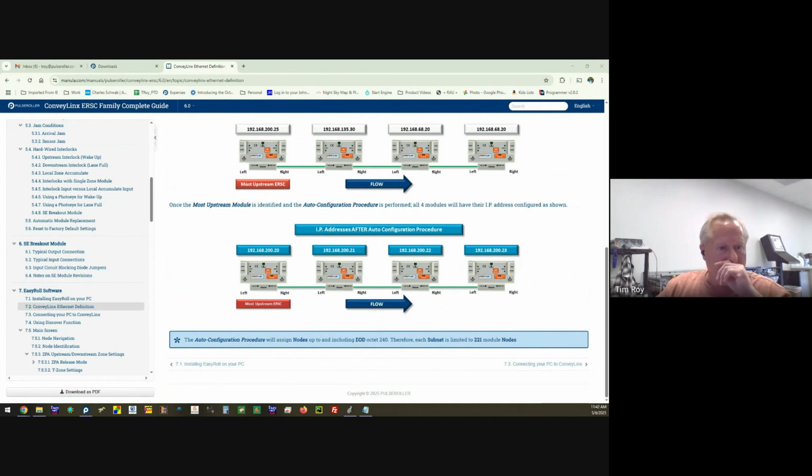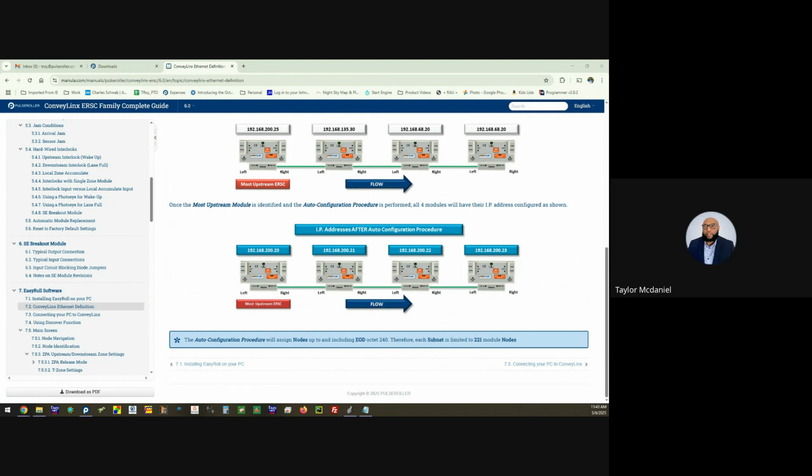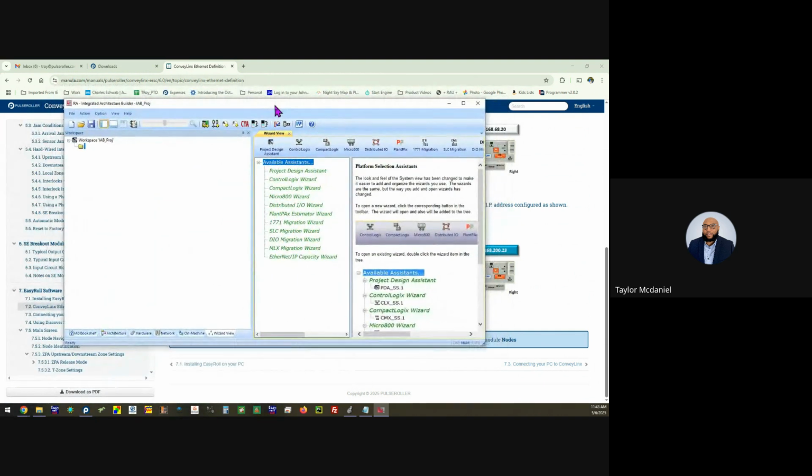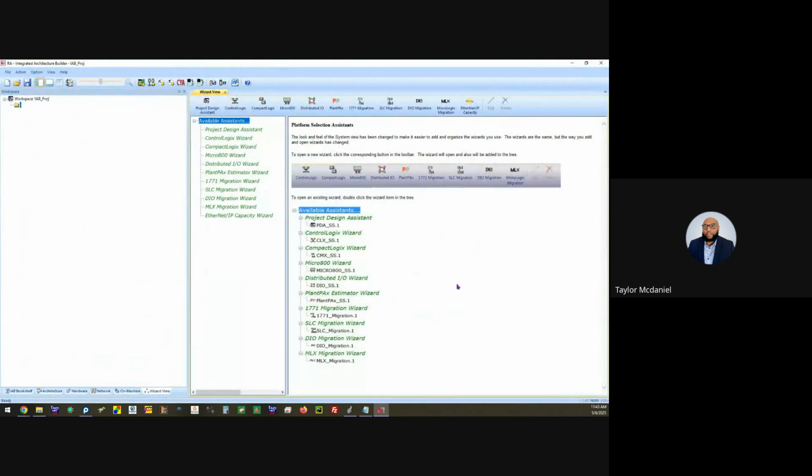Let me see. I'm looking for something here. There you go. He said 200 RPI and most of them are massively slow. Task is steady. I think the PLC was on a continuous task scanning at 8 milli, but we have had peaks of almost 16 milli. I believe those peaks are related to the amount of traffic caused by the ERSC card, but he doesn't understand that the staggered RPI would improve communications. So all of them right now, I think, are still defaulted to the same RPI. I think he just disabled keying for the moment.